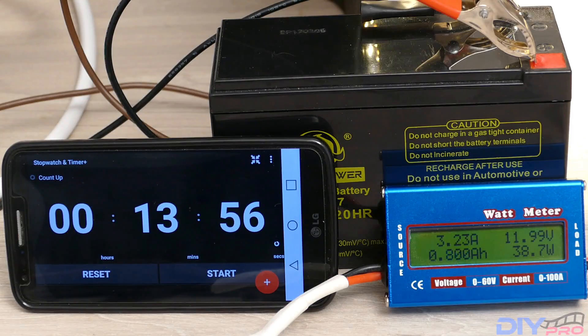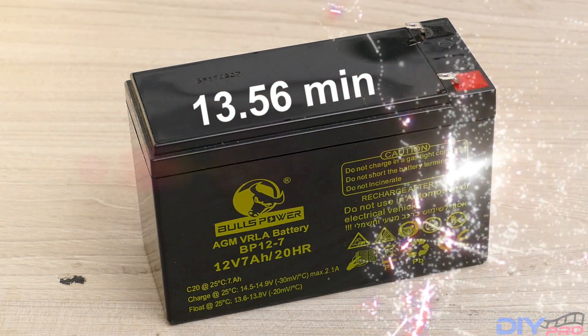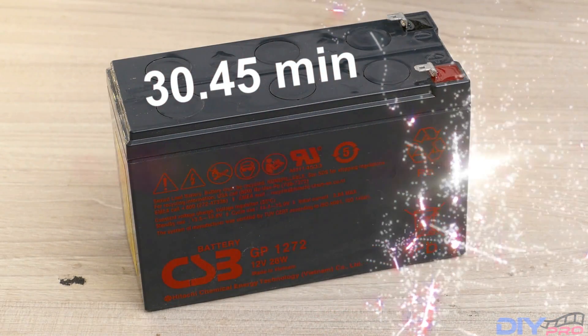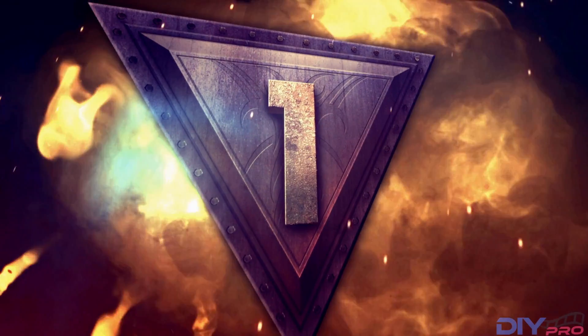After 13 minutes and 55 seconds it's below 12 volts. So let's recap: number four is the AGM BP12-7 with 13 minutes 56 seconds; number three is the CSB with 30 minutes 45 seconds; and number two is the DataSafe 12HX35T with 41 minutes 53 seconds.